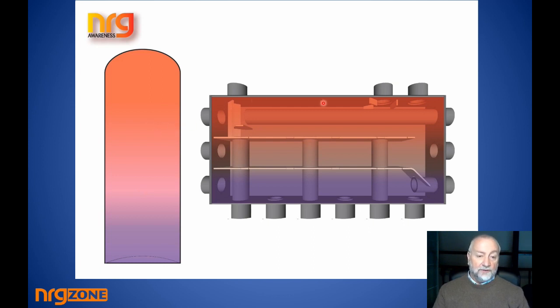Now, if you have an energy zone, you certainly have the stratification because the heat from the appliance or appliances comes into the top chamber, which we'll go through, and the return water coming back from the zone goes into the chamber here that I'm identifying as the return chamber, but you'll see in a while that not necessarily so. But in this standard ordinary example, the coldest water is in the bottom chamber. That's what's collected by the appliance and brought back to the boiler. So you have stratification by the natural fact that hot water is less dense and therefore lighter, and you have the heavier water at the bottom.